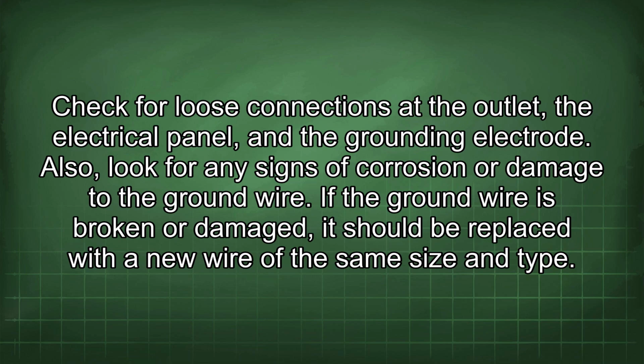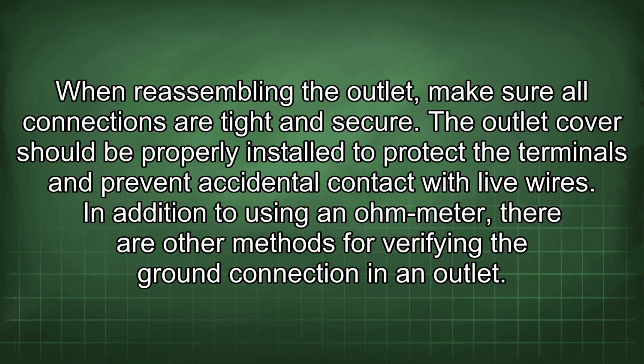Also, look for any signs of corrosion or damage to the ground wire. If the ground wire is broken or damaged, it should be replaced with a new wire of the same size and type. When reassembling the outlet, make sure all connections are tight and secure. The outlet cover should be properly installed to protect the terminals and prevent accidental contact with live wires.